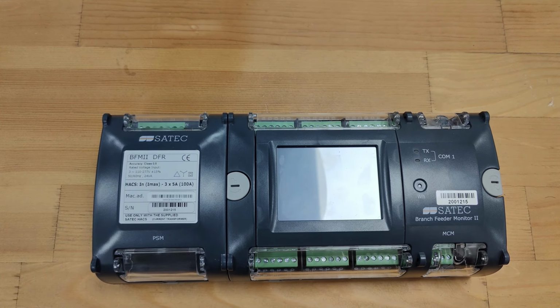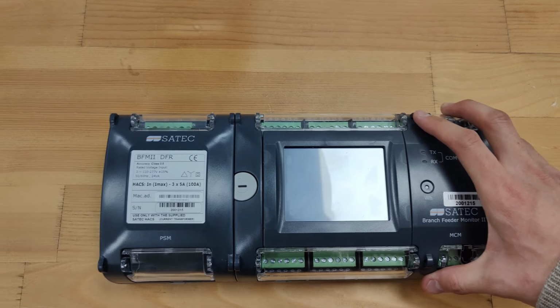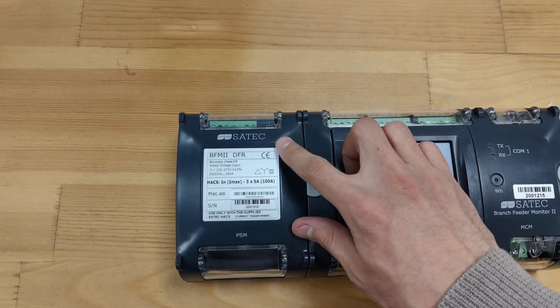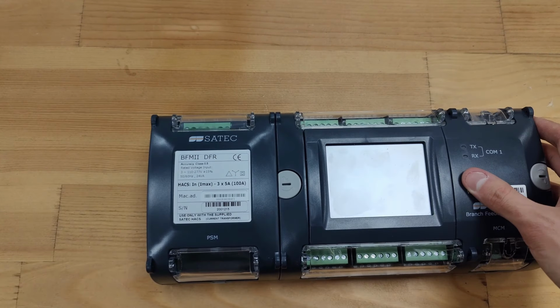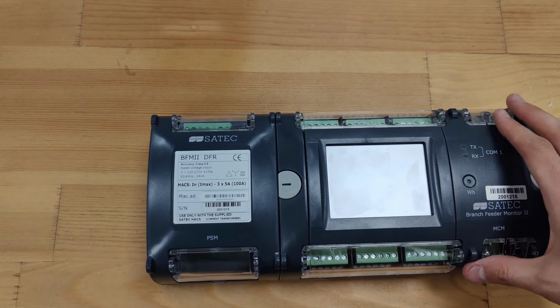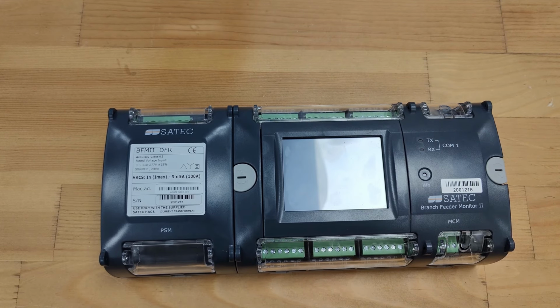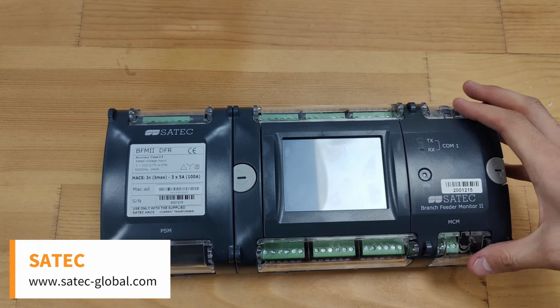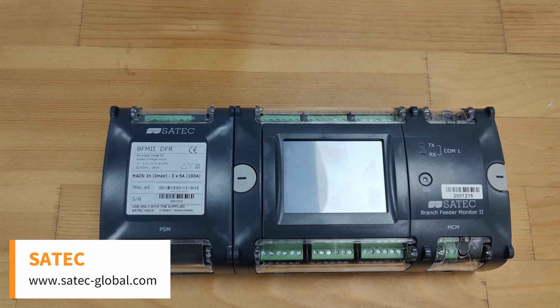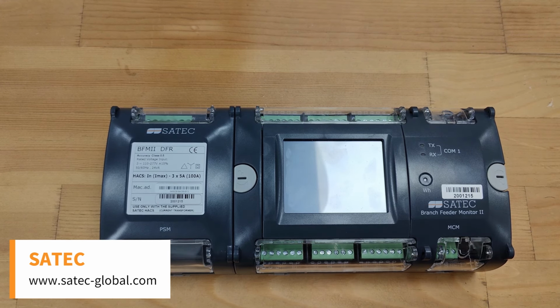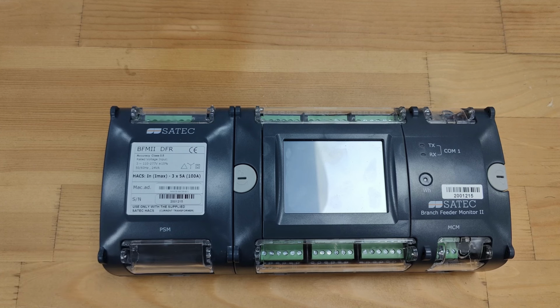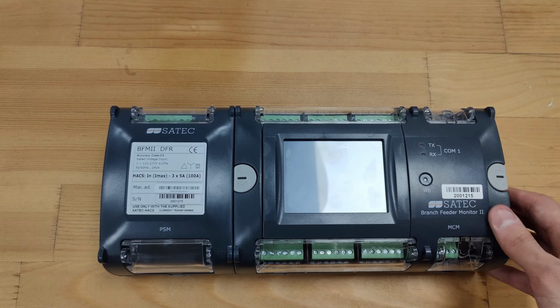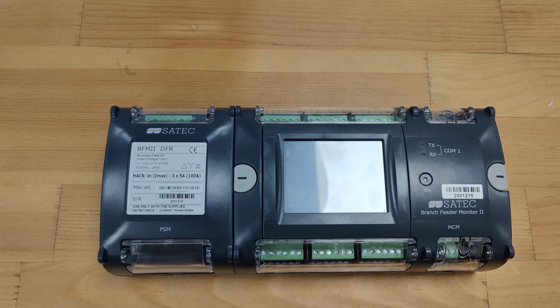Good afternoon. In today's video we're going to talk about the BFM II device. The abbreviation of this device is a branch feeder monitor. This solution allows you to monitor data on power consumption and parameters of electricity from several feeders simultaneously using only this device. I have on my desk right now a modification of the device with the function of recording emergency events, digital fault recorder. It allows you to record short circuit currents on individual feeder branches. That is why it's labeled with the DFR.